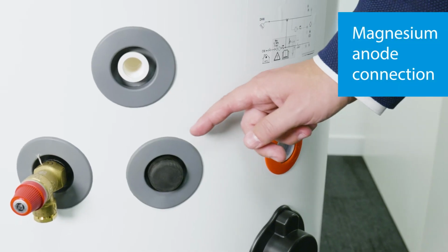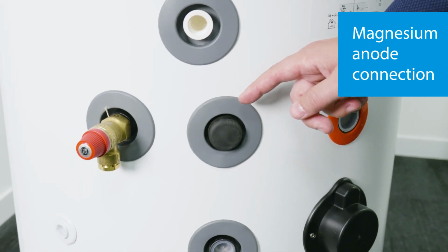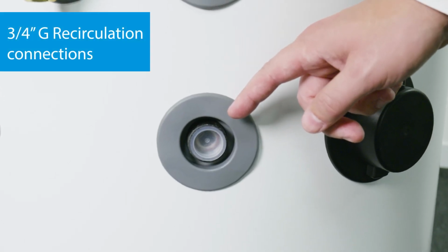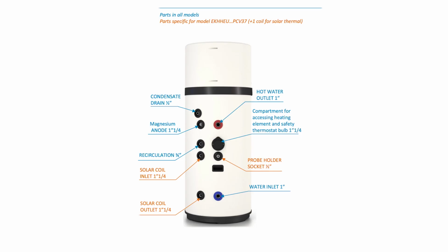Then we have a connection for the magnesium anode to prevent corrosion of the tank, and then recirculation connections, like for a secondary return, to help keep the water warm. A third-party external pump is required for that also. The pump can then be connected to the heat pump and scheduled periodically, or just switched on or off. There are also some specific inlets to allow for the solar thermal connection, or the bivalent source, i.e. the connection to the solar coil, for example. However, these connections are only available in the so-called PCV37 models, which you can find in the material reference.